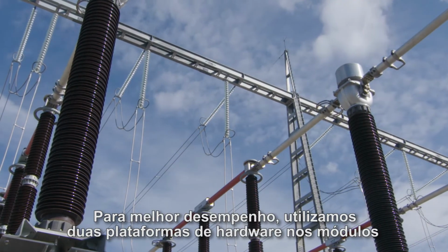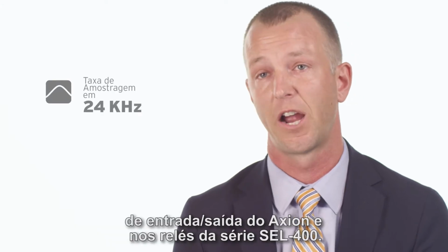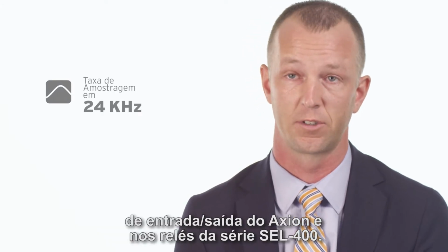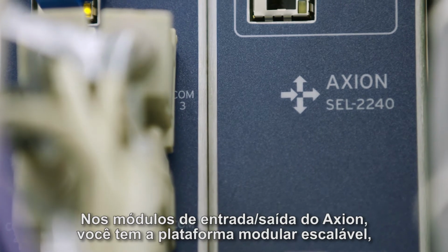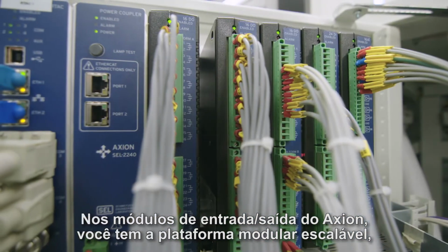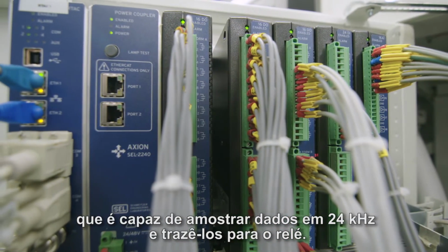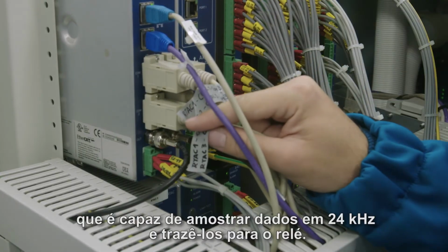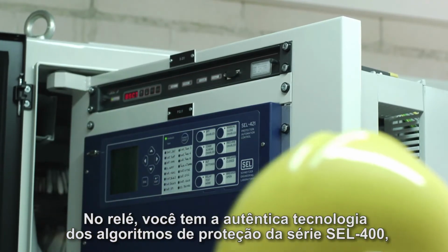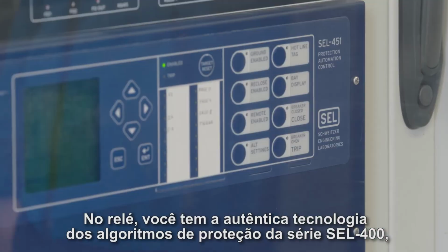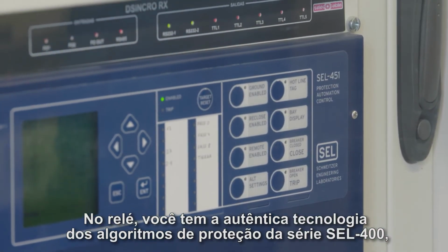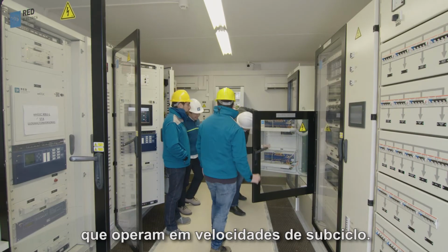For performance, we take two hardware platforms: the Axion I/O modules and the 400 series relays. On the Axion I/O modules, you have the scalable modular platform that's able to sample data at 24 kilohertz and bring that into the relay. On the relay side, you have the proven technology of the 400 series protection algorithms that operate at sub-cycle speeds.